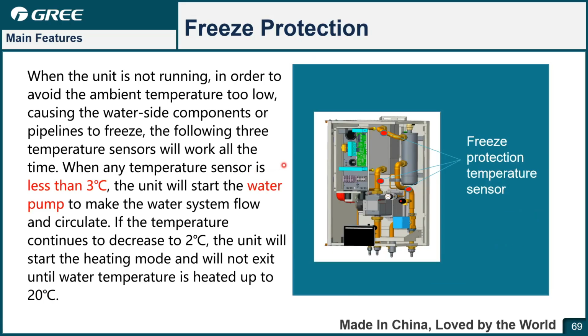Freezing protection. For the VERSATI 3, the hydro box is very easy to be frozen in the cooling mode and in winter. So in the hydro box, on the copper pipe, we put 3 temperature sensors to detect the temperature value. If at any point the temperature is lower than 3 degrees Celsius, the water pump will start to circulate the water. And if at any point the temperature is lower than 2 degrees Celsius, the unit will start to do the heating mode, until the water temperature is higher than 20 degrees Celsius, and then it will stop the anti-freezing protection.